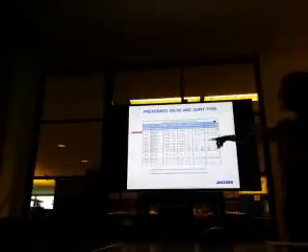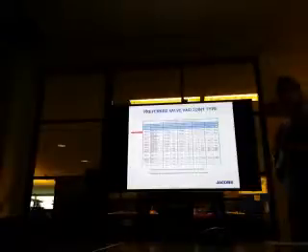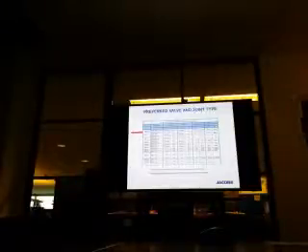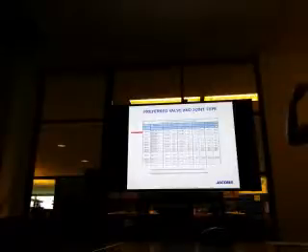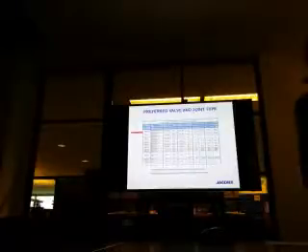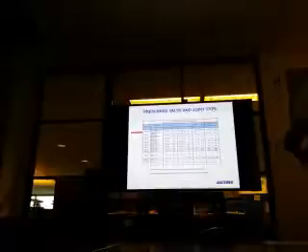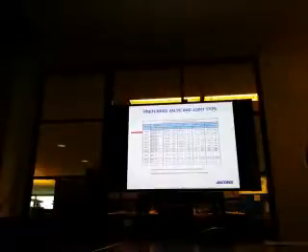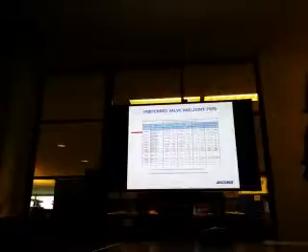The larger sizes, for large bore, we have butt weld. And that's where we have two pieces of carbon steel pipe. They come together at a 37.5-degree angle, and they weld them together. And if you look here, it says that we have it butt welded or flanged. So this still agrees with this. Our preference is every fitting and each piece of pipe are butt welded together.